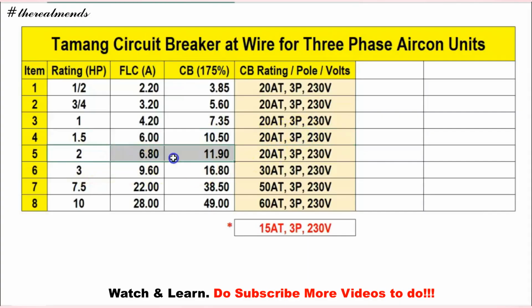Sa 2 HP, so 20 ampere trip again 3 phase. Sa 3 HP, 30 ampere trip na 3 phase. Sa 7.5 HP, so 50 ampere trip 3-phase. Sa 10 HP, we have 60 ampere trip 3-phase.